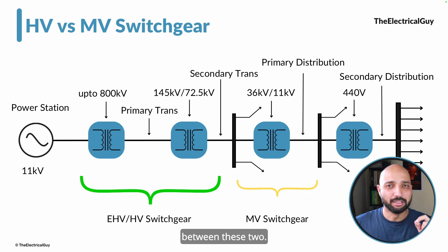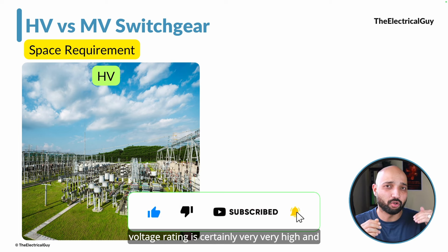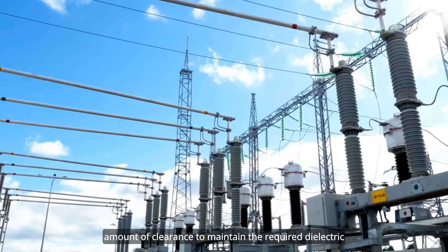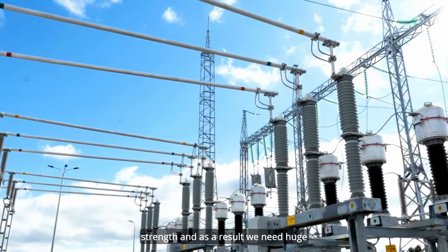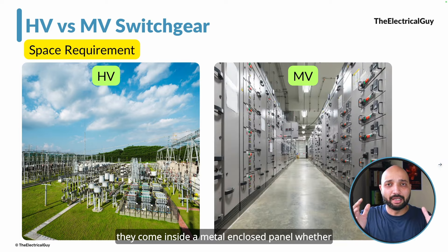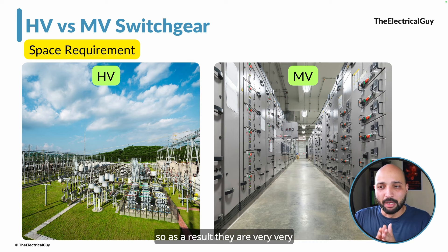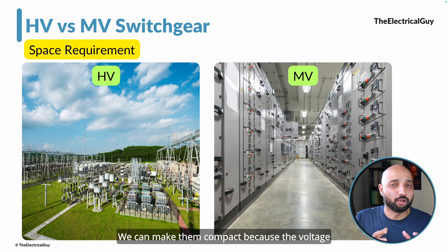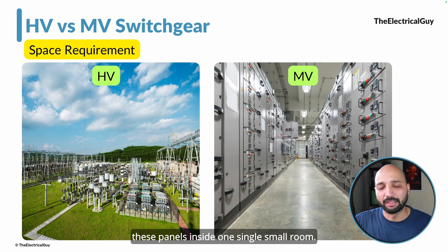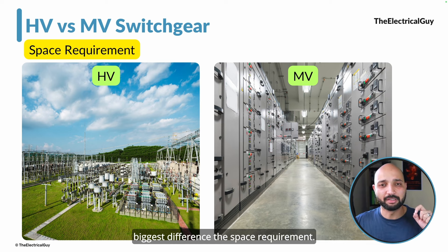Now let us understand the differences between these two. Starting with the first and most important difference: space requirement. When we talk about high voltage, the voltage rating is very high, and when using air insulated switchgear we need to maintain certain clearances to maintain the required dielectric strength, requiring huge land. On the other hand, medium voltage switchgear comes inside a metal enclosed panel — AIS or GIS — and is very compact, allowing many panels to fit inside one small room.